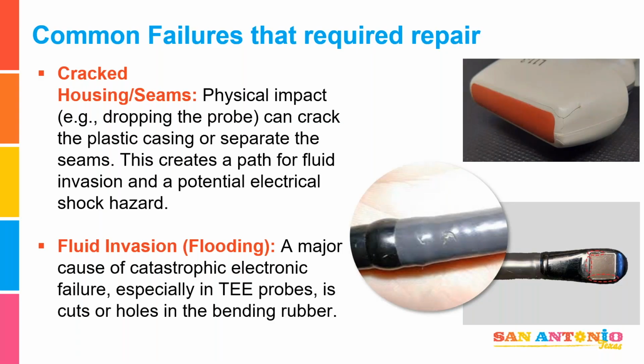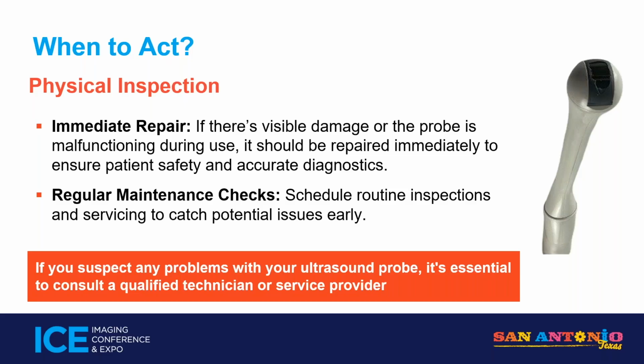Physical inspection. Again, I do them all the time, anytime I'm in front of an ultrasound system. Immediate repair. If there's visible damage or if the probe is malfunctioning during use, it should be repaired immediately to ensure patient safety and accurate diagnostics. Okay, and it should say diagnosis, but bottom line is if you have any image quality issues, anything that makes you feel like this is substandard, a crack, a missing lens material, electrical safety is not passing, it's leaking, anything like that, get it taken out of service. Try to get a loaner so you're not without the probe, and get it evaluated.